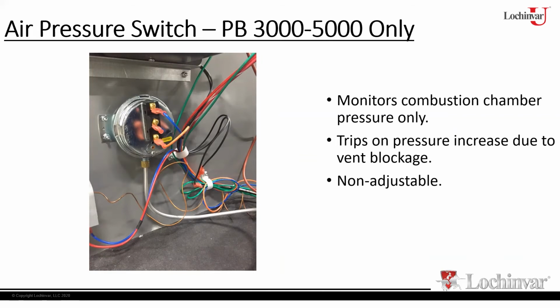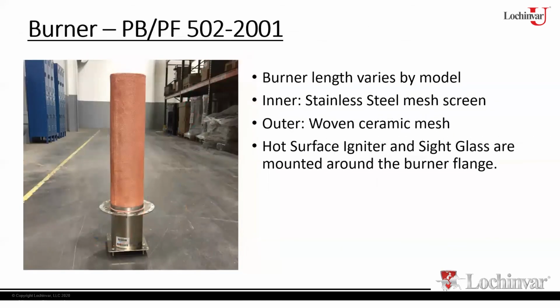So now we've got our combustion system as far as the gas train, the blower, the pressure switches, and the safeties monitoring that. All of that then feeds down into the burner. So the last part of the combustion process is the burner itself. Now, your 500 through your 2 million, in this case, we're using a ceramic fiber mesh. This gives it the orange look that you see here. The inner liner is a stainless steel mesh screen covered by this ceramic fiber.